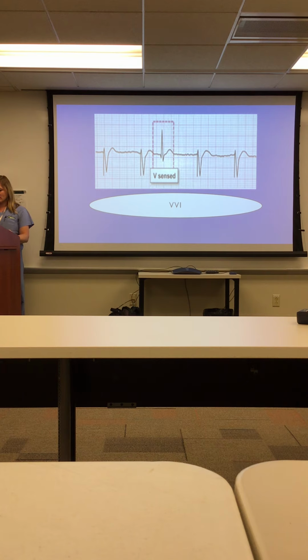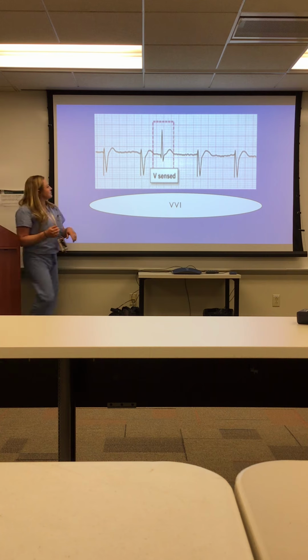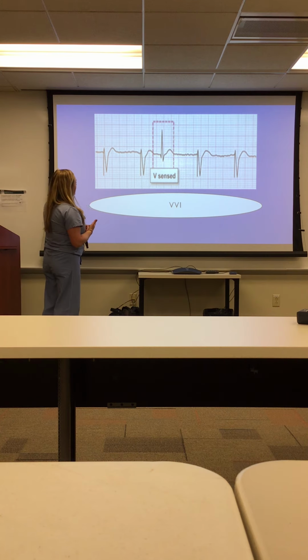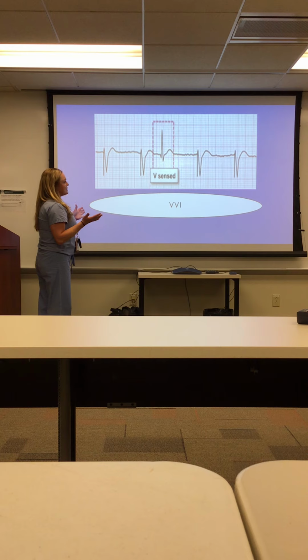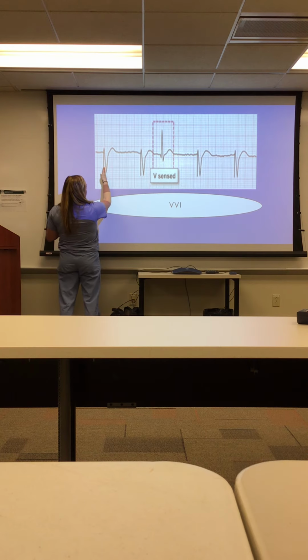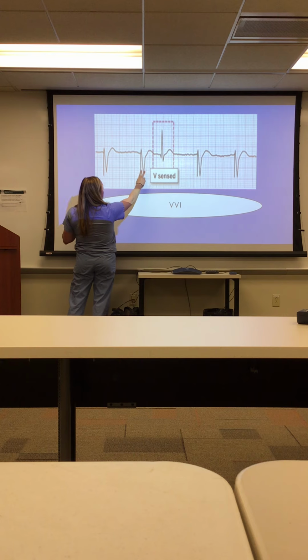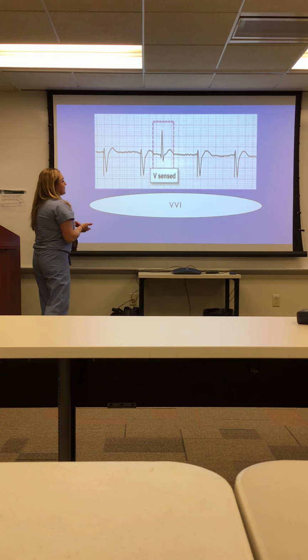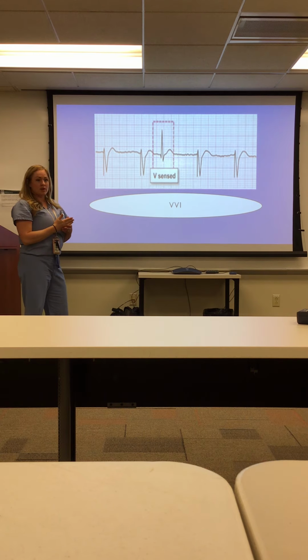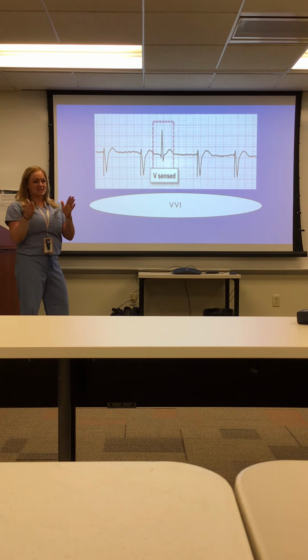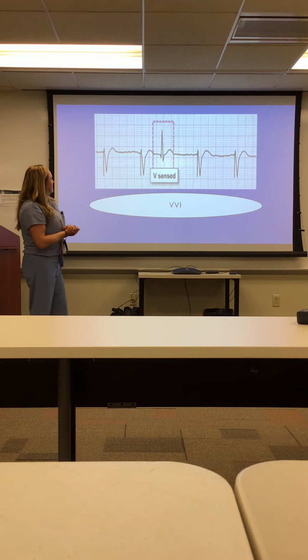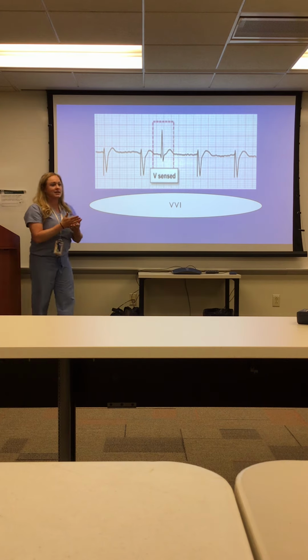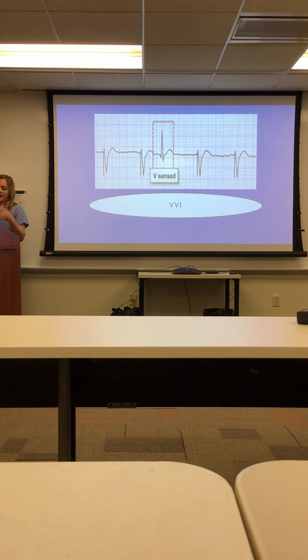Okay, and then in this scenario, we've got VVI pacing. Say the programmed lower rate is 60. We've got a nice paced beat here with a wide QRS. We know we're capturing, and then we see an intrinsic beat come through. That says the device was able to sense the R wave appropriately, within that 60 beats a minute window, so it's not going to deliver a paced beat. If it's outside of that, or say they're in the 50s, that's when you're going to see a paced beat every time. So it's acting appropriately and withholding pacing as long as the intrinsic rate is higher.